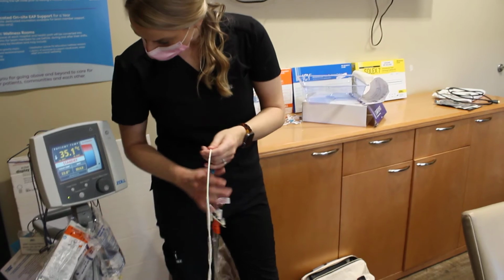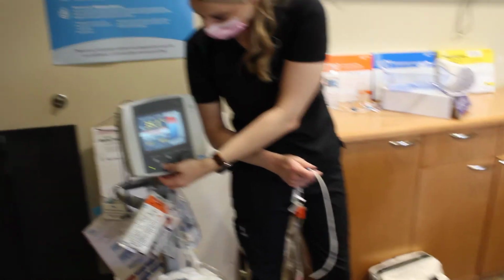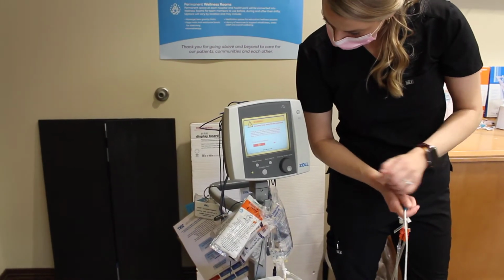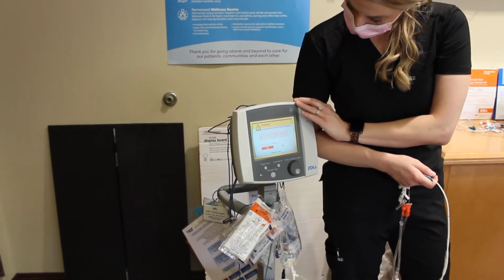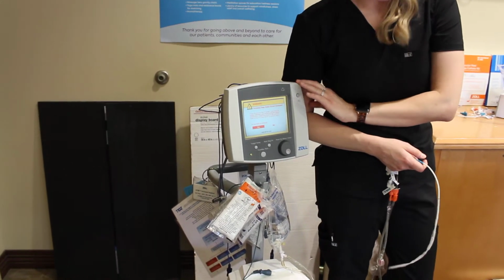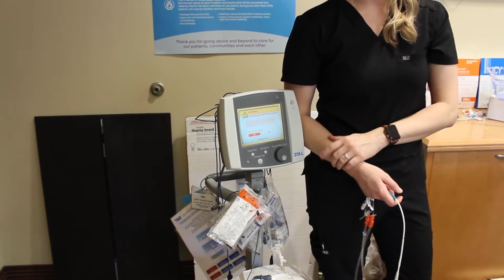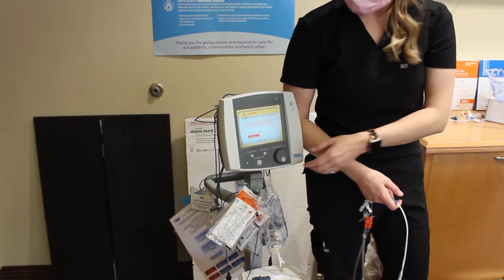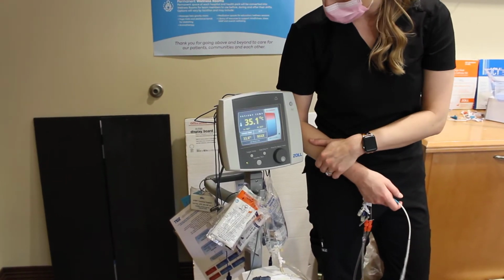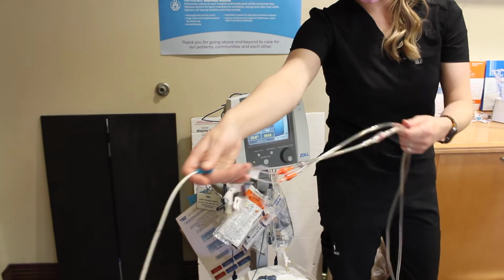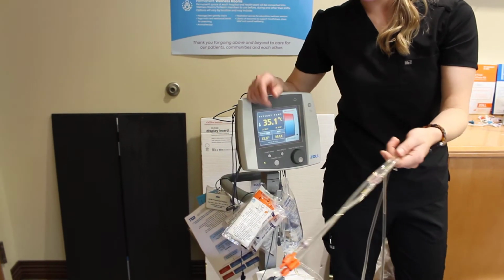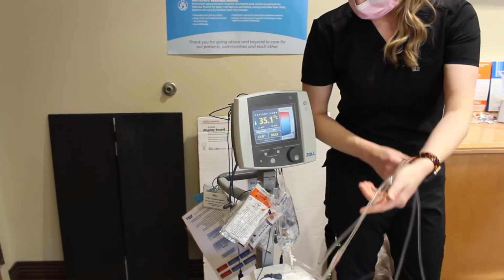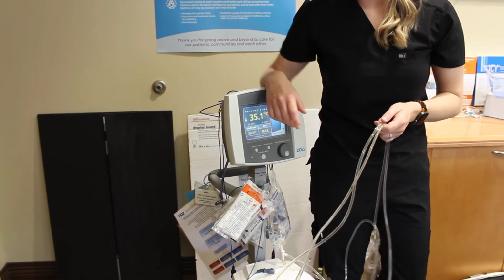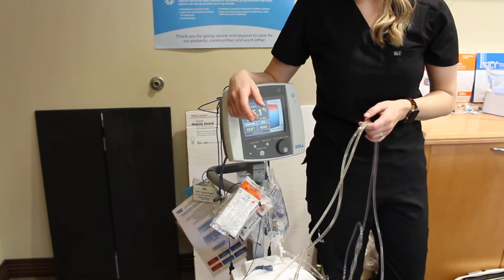And when we are good to go, press run. We've got a warning coming up saying secondary temp probe not connected, and that's fine. You can run this machine with 1 probe if you want to. You don't need 2, so we'll press yes that we wish to proceed. And if you want to hold on to that and take a look at the catheter. Okay. You can see the catheter filling up with the saline.